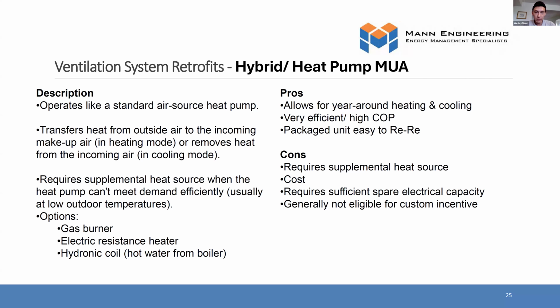Now, this is a new incentive from Enbridge. A hybrid heat pump pretty much operates like a standard air source heat pump, where it's extracting heat from the atmosphere or rejecting heat into the atmosphere. One of the main benefits is that it can do heating and cooling. So if you have a makeup air that has cooling, this is a good option as a retrofit, because the heat pump will do both and provides year-round heating or cooling. It could also be a good option if you're looking to add cooling to your corridors as an additional measure for your building.